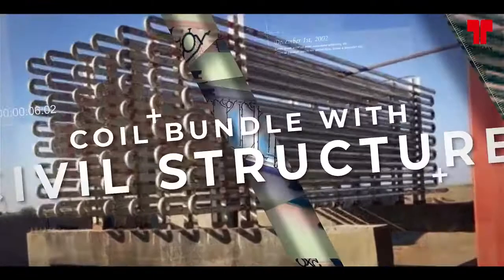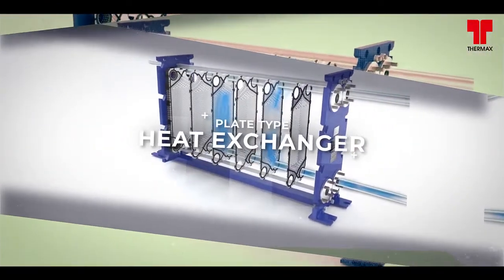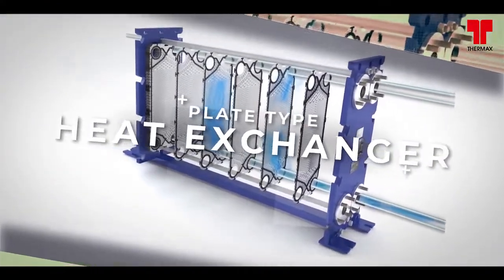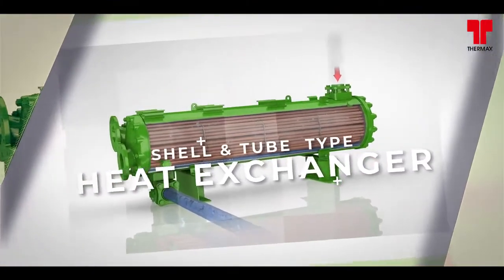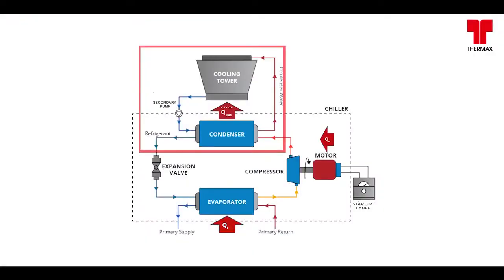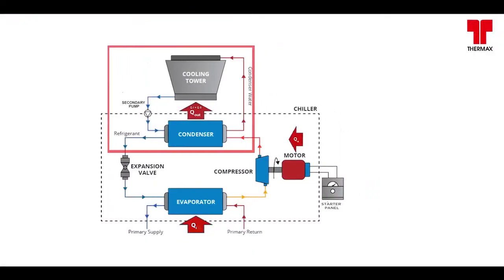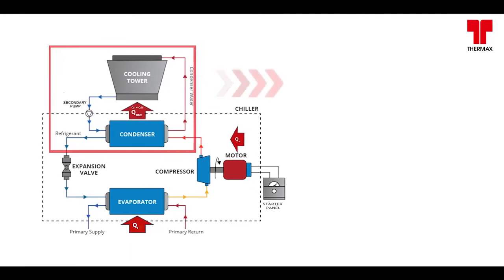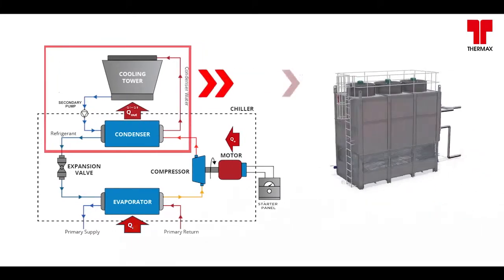The conventional condensers come in the form of traditional coil bundle with civil structure, or a combination of either a plate-type heat exchanger or shell and tube-type heat exchanger, and open-loop cooling tower with circulation pump. Our innovative evaporative condensers integrate the intermediate heat exchanger, secondary pump piping, and open-loop cooling tower into a single unit.